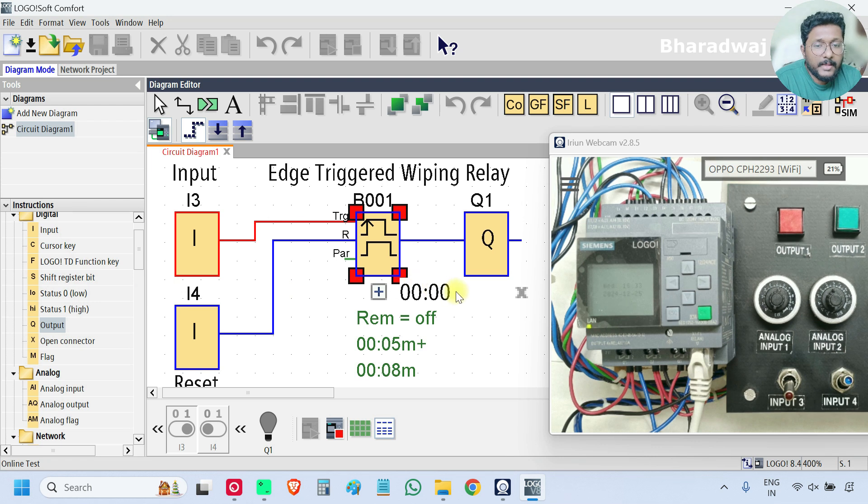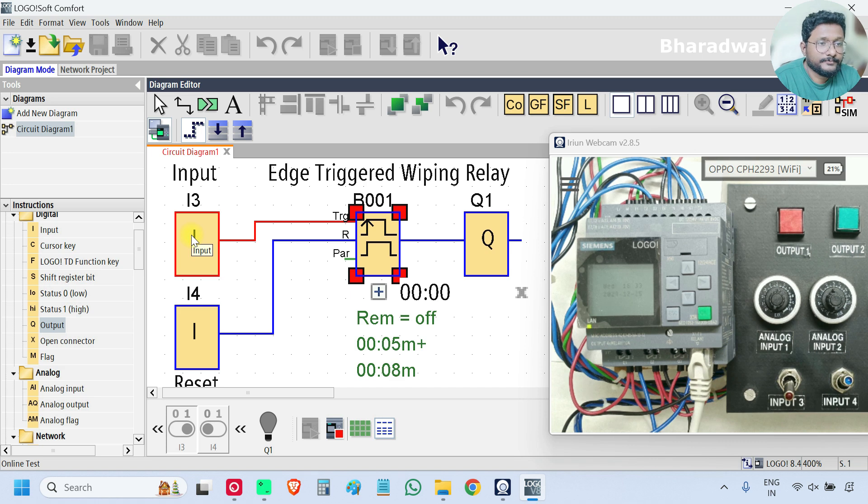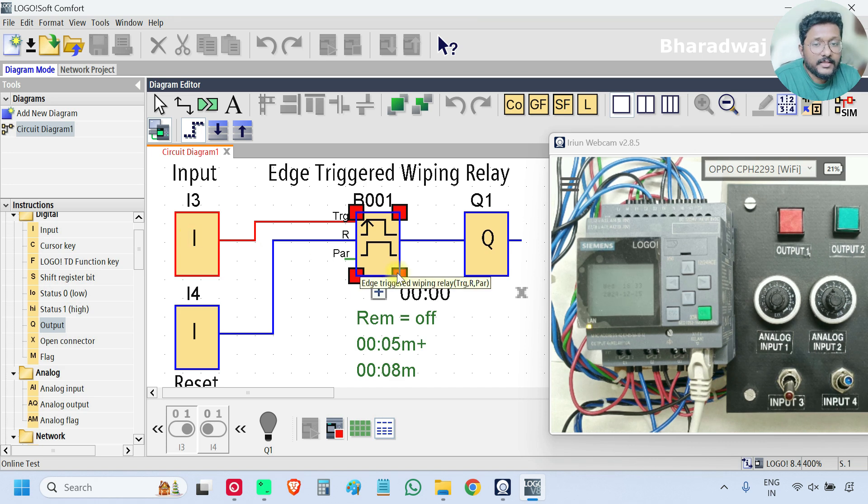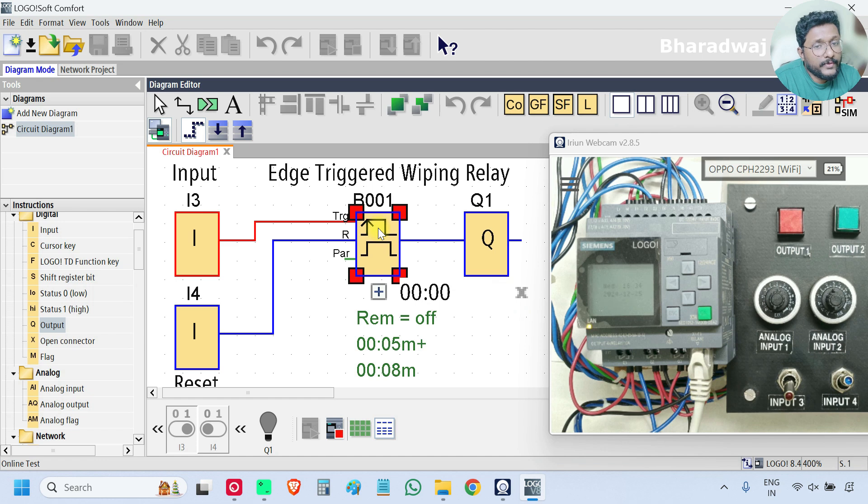See, the timer is not started even though the input is on. Why? Because this block input is operated when the input changes its state from zero to one. It needs rising edge input.